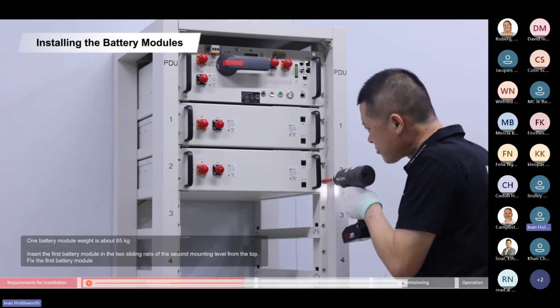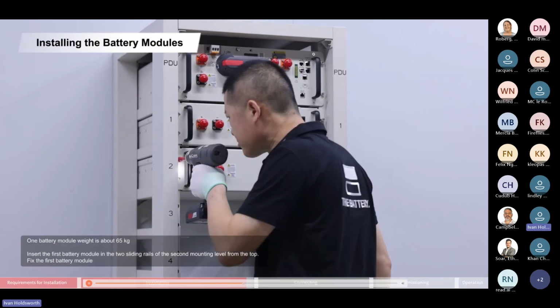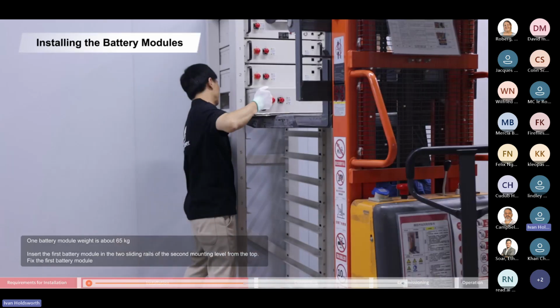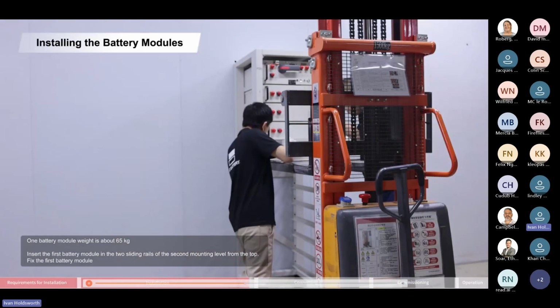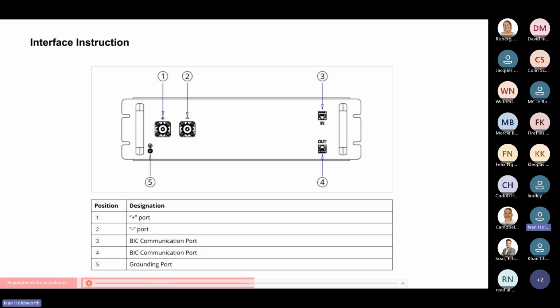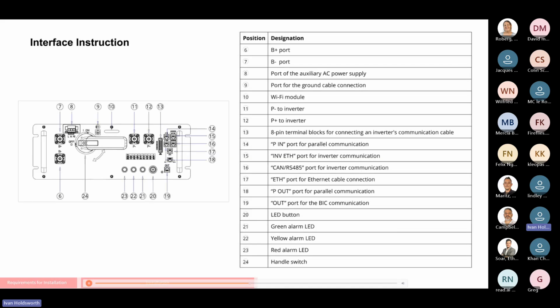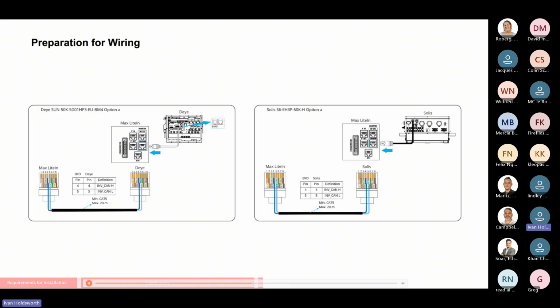It's very important when expanding the battery bank. Supposing you've got 7 battery modules and you'd like to add an extra 2, the existing modules need to be at the same SOC as the battery modules that you're adding, which is probably going to be about 30%. And here you can see the various parts of the PDU and how to connect to your inverters.